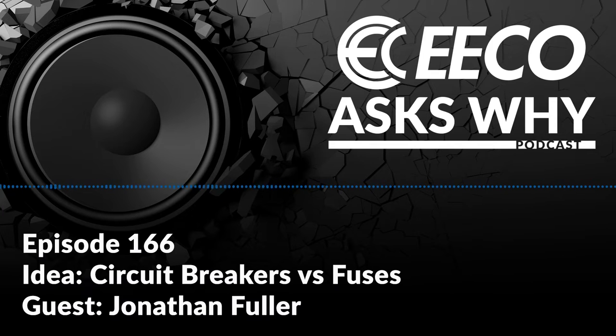So whereas they might need a 20 amp slow blow fuse, they might end up putting in a 25 or 30 by accident, not realizing that they grabbed the wrong one, or they might be out of it. Whereas with the circuit breaker, some of the advantages are, when it trips, you're going to be able to verify the reason that it tripped, make sure that reason doesn't exist anymore, and then you're going to be able to reset that circuit breaker and go on your way.